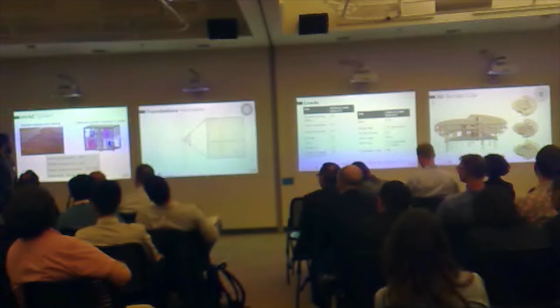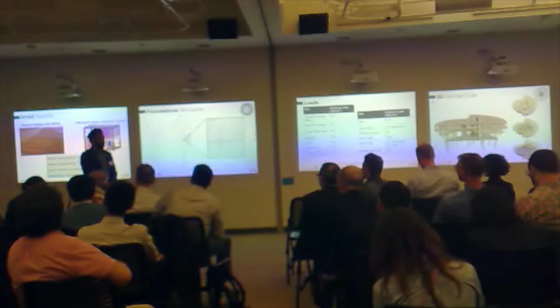Let's talk about the HVAC system. These are fairly standard values for Class A indoor air: in summer we maintain 24 degrees Celsius, in winter 22 degrees Celsius, and relative humidity of 55% plus or minus 10%. Because it's a university building, noise has to be controlled under 45 dB.